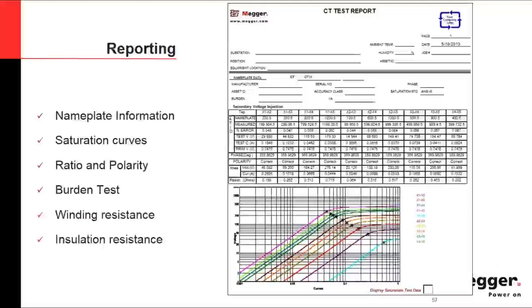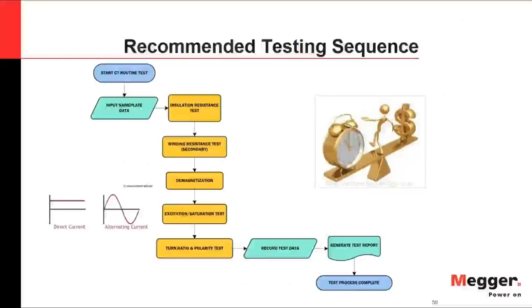After completing the tests, reporting is critical. Make sure your final report includes complete nameplate information. When you fill in nameplate details — accuracy class, and whether this is an ANSI or IEC standard CT — the test set will configure itself to test the unit according to that specific standard. Your report should include: saturation curves, ratio and burden test values (both measured and estimated at various percentages), winding resistance, and insulation resistance.